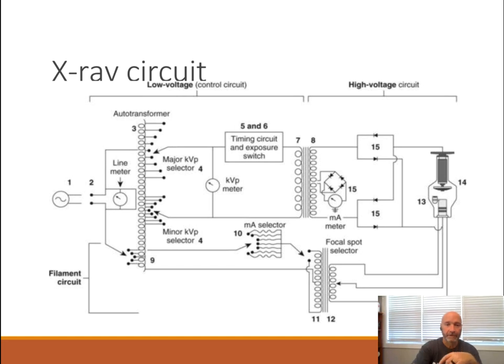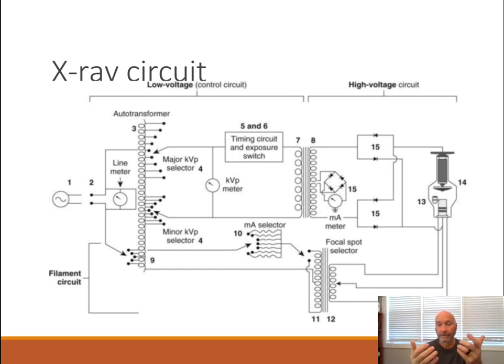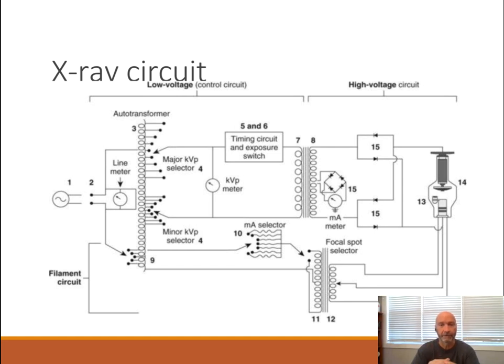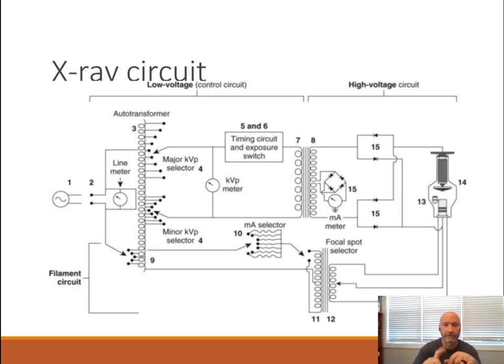This is a KVP meter, just to tell us how much KVP we're going to eventually create. Some textbooks, including Bouchon, will call this a pre-reading KVP meter, which is a better description, because we don't have KVP yet — we just have voltage. So we have the autotransformer, and then we've got something else over here that has two coils. The distinguishing characteristic of the autotransformer is it only has one coil.